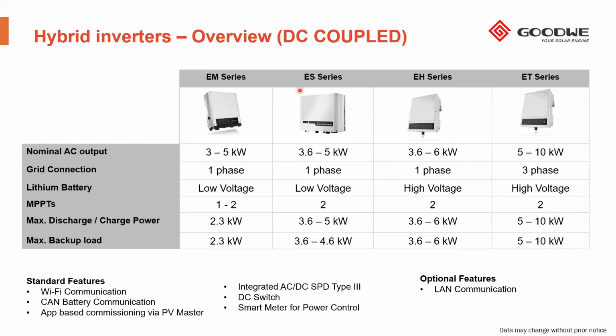If we move along to the ES series, this inverter is a single phase low voltage inverter as well. It's available from 3.6 to 5 kilowatts. Each inverter in this range has 2 MPPTs, and the maximum discharge and charge power is 3.6 to 5 kilowatts. The maximum backup load is 3.6 to 4.6 kilowatts, depending on which inverter you choose. The ES inverter is like the big brother of the EM inverter. If you have a customer with a relatively small house who is relatively price sensitive, then an EM series inverter would be the way to go. If you have a customer who has a little more money to spend and bigger backup loads, then the ES series would be the choice for this end user.